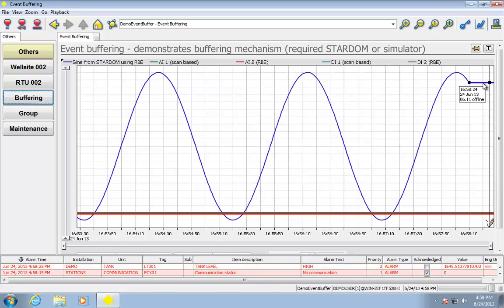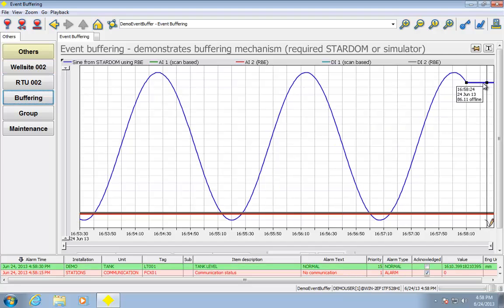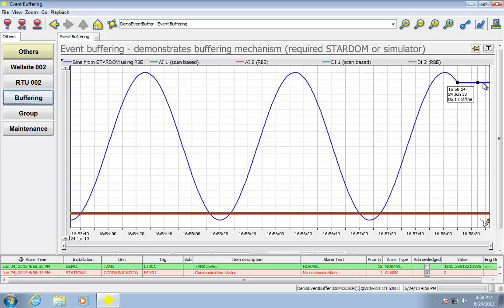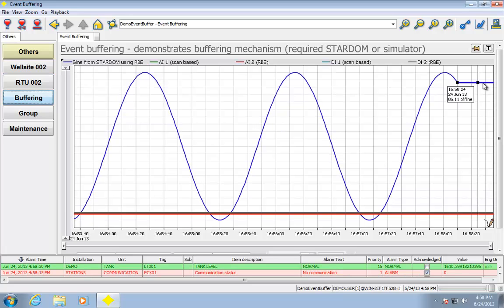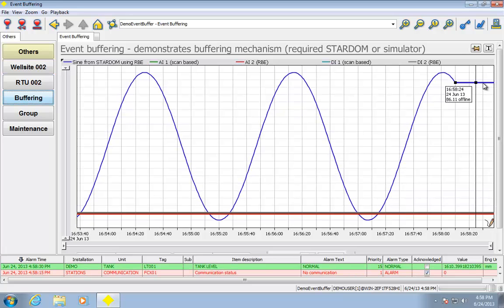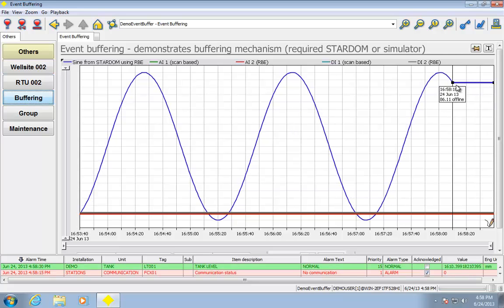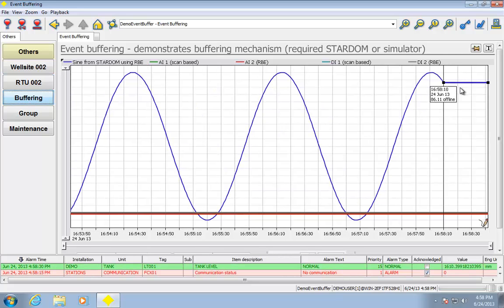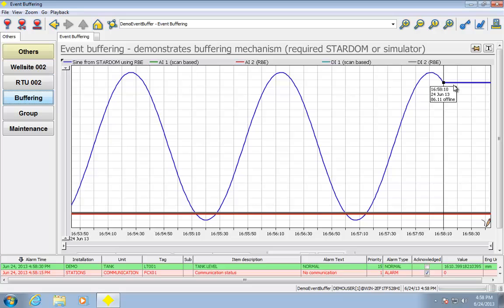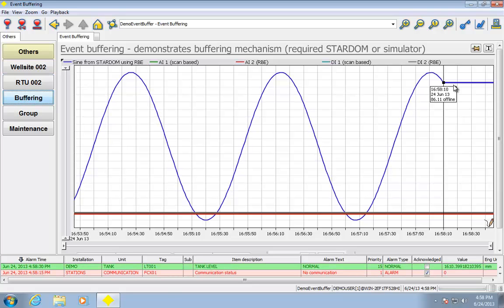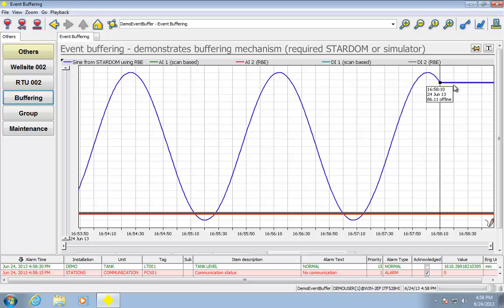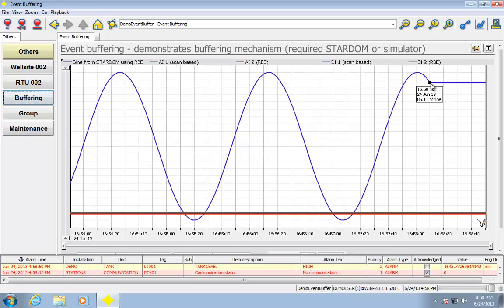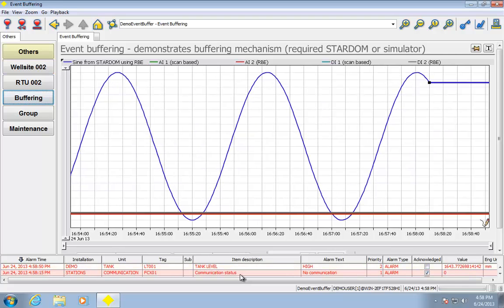So we can see right now at the bottom my communication status went bad, and we can see on the trend that essentially these samples of data I was hoping to get, I'm no longer getting them. It's offline. I'm going to go ahead and reconnect the network to that controller, and what we should see after a few seconds is the communication status is going to go good, and then we'll actually see the trend get backfilled.